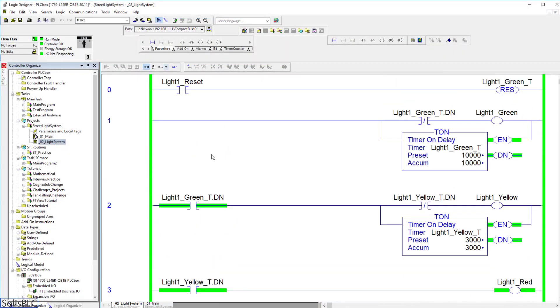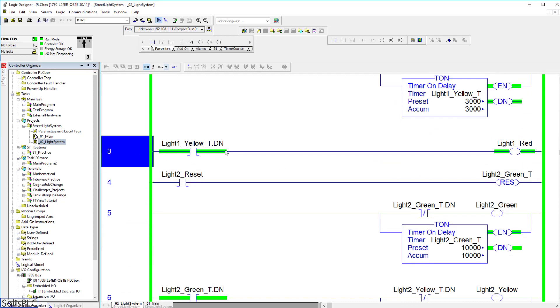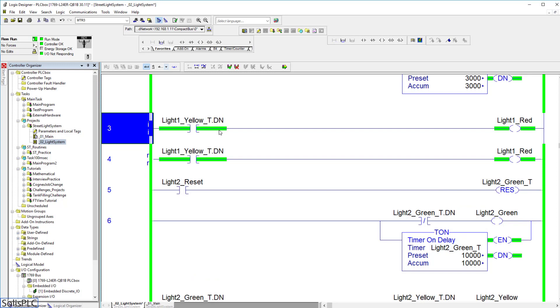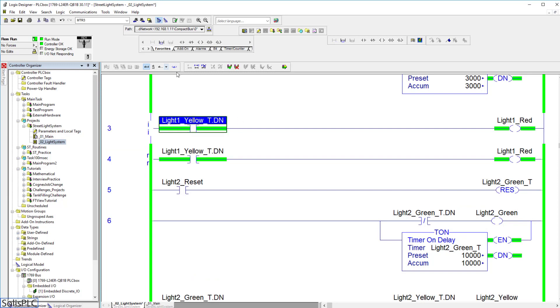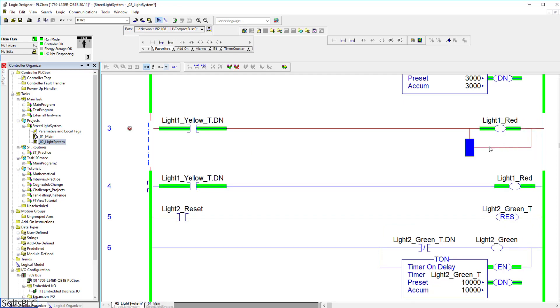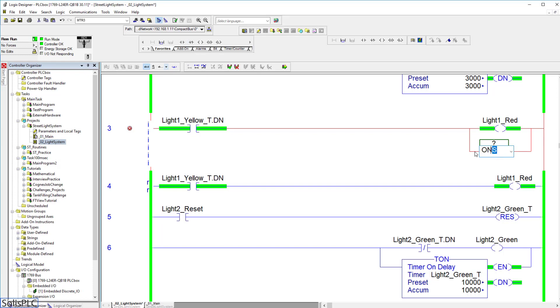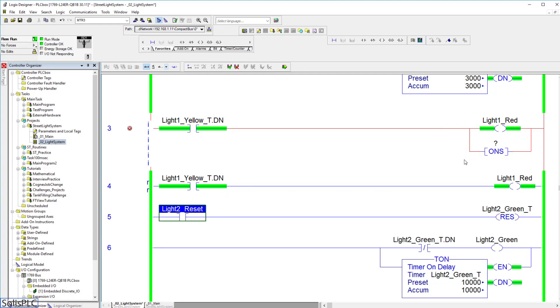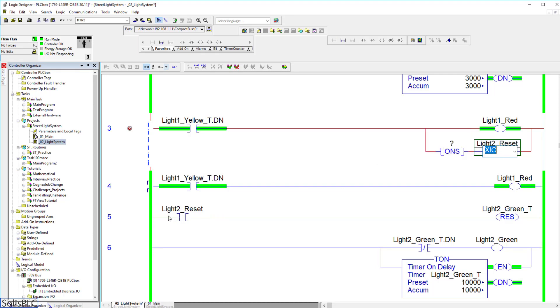The first thing we're going to do is implement the handshaking. Once this light has finished into a red state, we need to transition the other light to a green state. We're going to double-click this branch to make changes on the controller. I'm going to use a one-shot instruction, which essentially allows the PLC to transition to a high for a single scan time. I'll click the XIC instruction, double-click the name, and type in ONS, which stands for one-shot. That one-shot is going to trigger the reset point for the second light, and I'll copy that tag into my branch and change it to an OTE to energize that reset for just a single scan time.